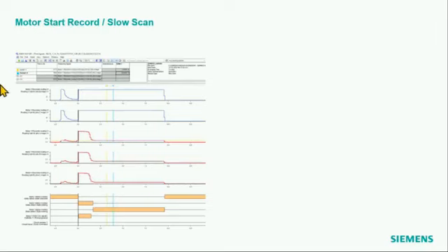And then I started this to create this motor start record, because I don't have a motor next to my desk. So I have to do this trick here at the end. And here you can see the starting currents and also binary signals for the startup of the motor. And you can maybe compare this with a record you had a couple of years ago or so and see if something changes in the motor. So just to register or see the behavior of the motor starting here.